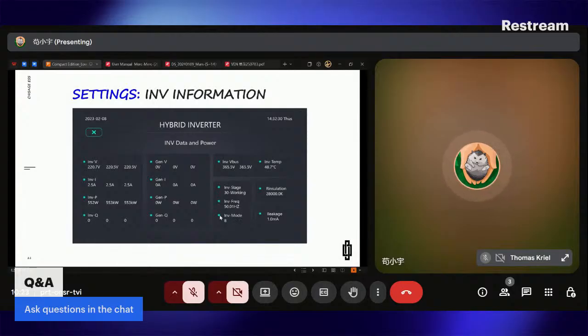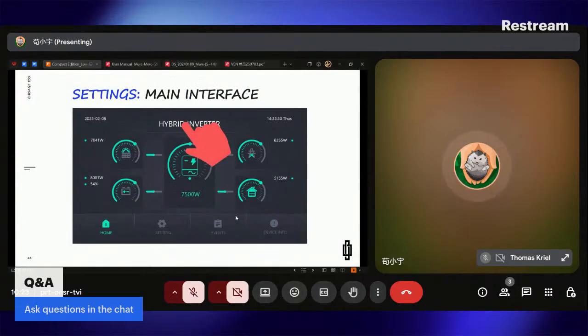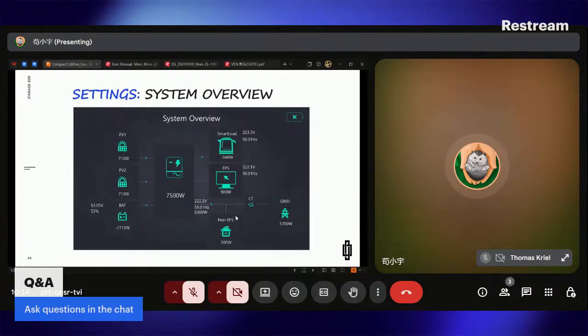And here we can see the INV mode. When you power on the inverter, usually it should be 8 here. And if you power it off, here will show 0. And sometimes you can see other numbers like a 5 at this part. That means the inverter is trying to activate your battery. Then let's go back to the main interface and click on the hybrid inverter text. When you click on it, you will see a more detailed graphic. You can see the power and the voltage on each part, and in the upper right corner, you can see the smart load here. If you connect the smart load, it will show like this. If you connect an AC couple or other things, it will show differently here.